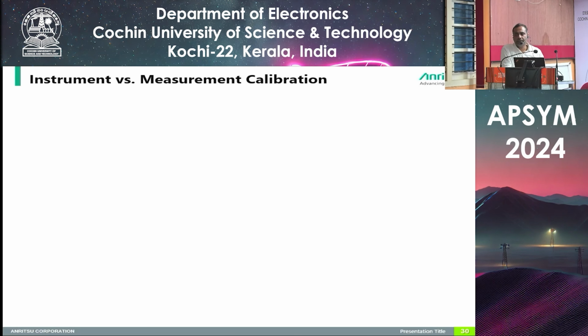No idea. So the spectrum analyzer is used to measure unknown signals. Okay, you can measure any signal. If you set the frequency range, suppose in the spectrum analyzer it goes from 1 Hertz to somewhere 20 gigahertz or 30 gigahertz or 43 gigahertz, we can set any frequency and measure whatever signal is radiated over the air, and we can measure the level and the noise level or harmonics in the spectrum analyzer.